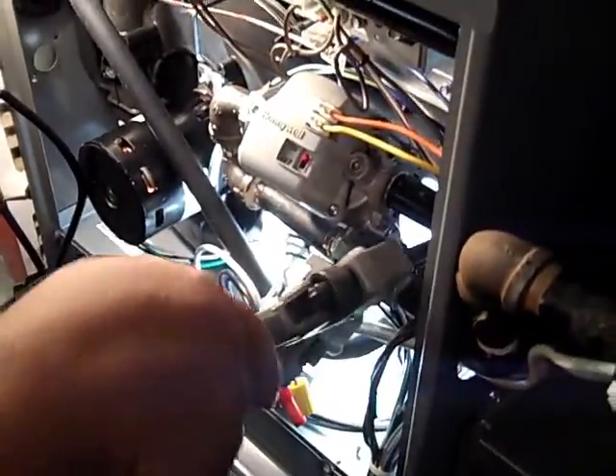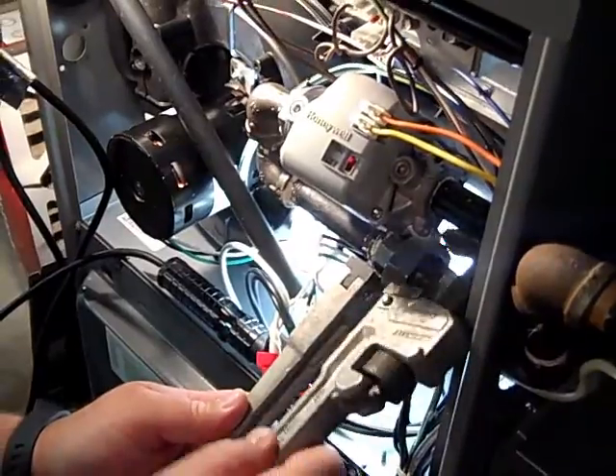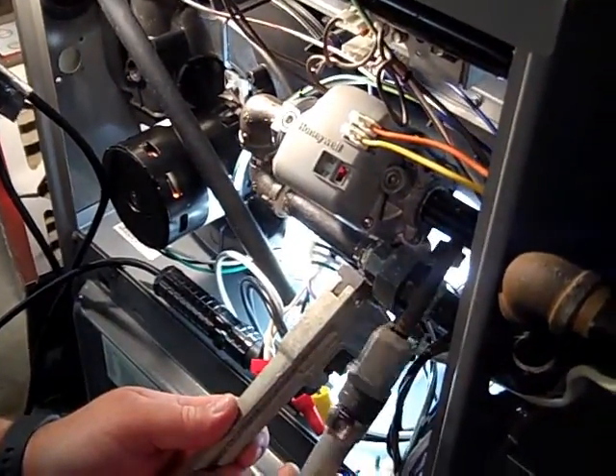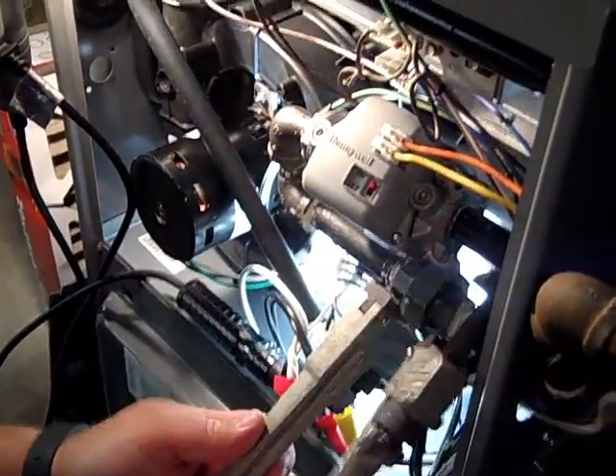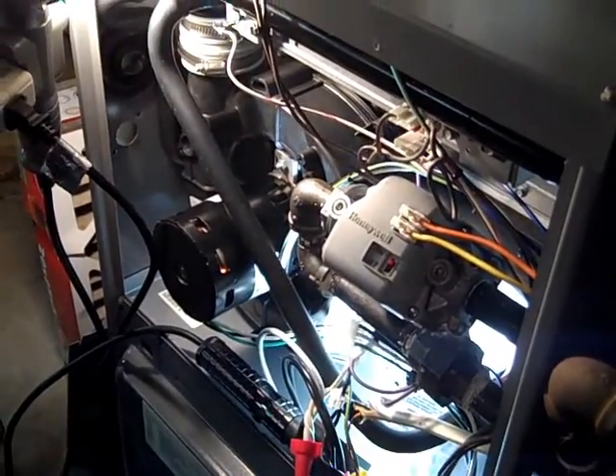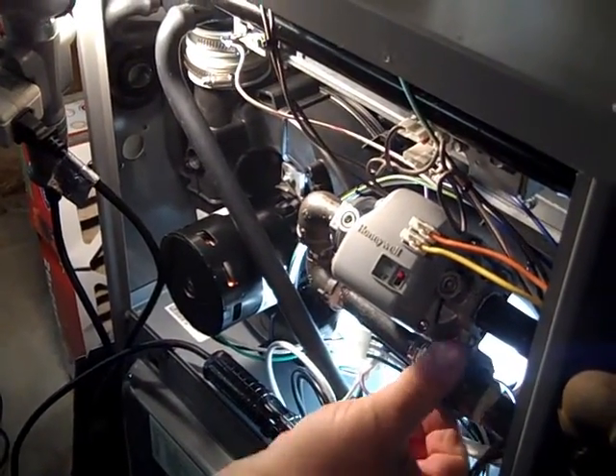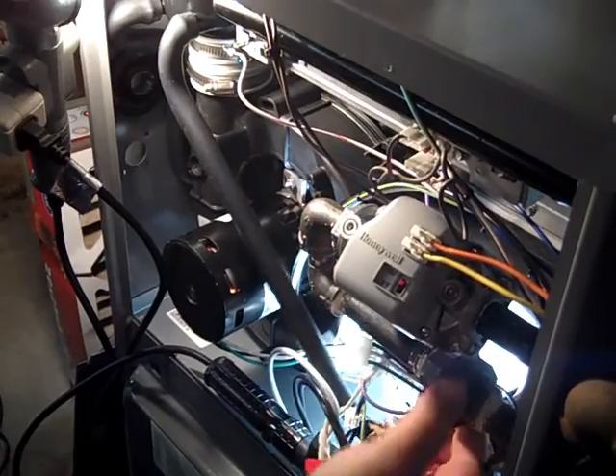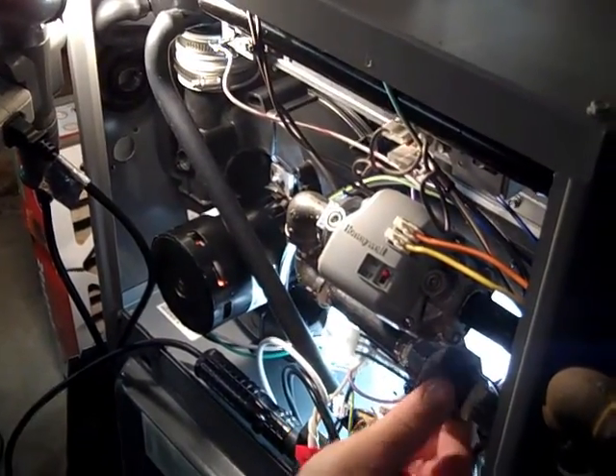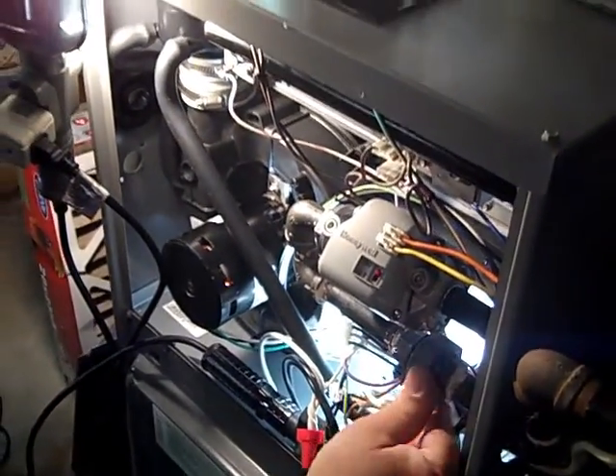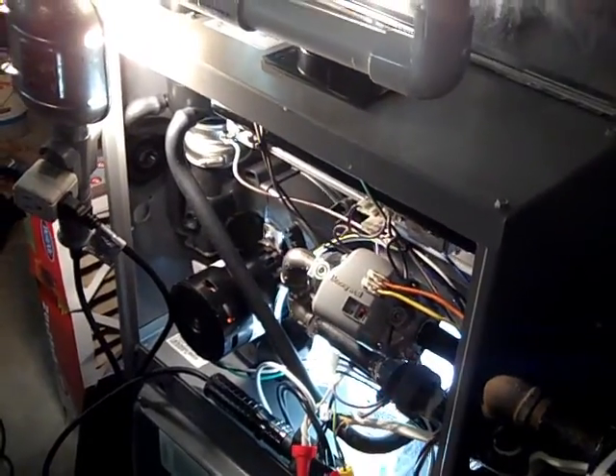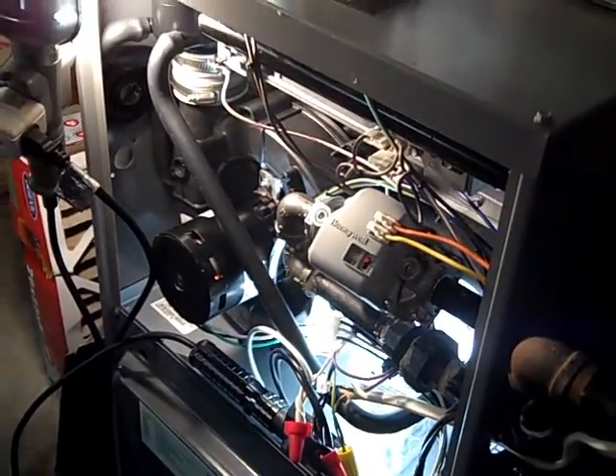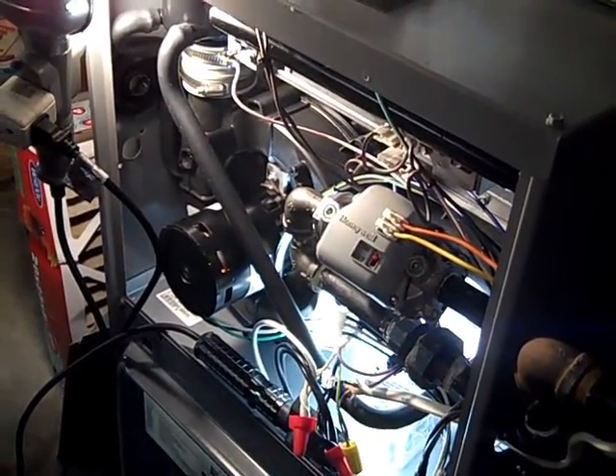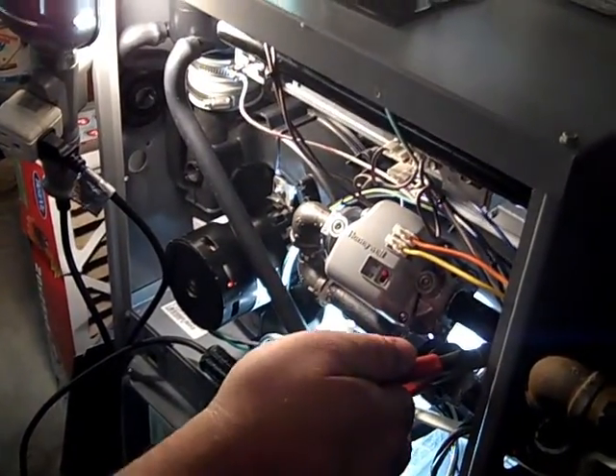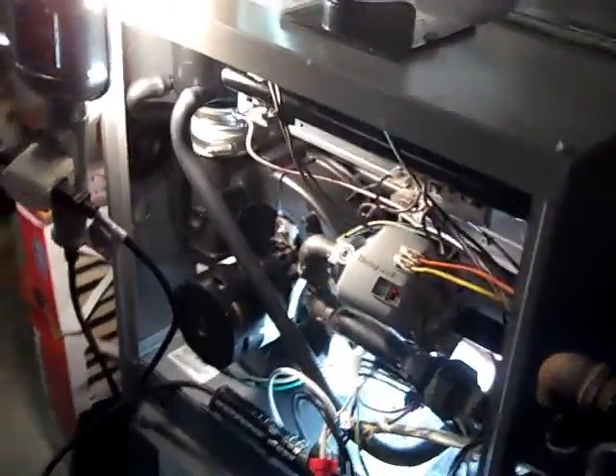Kevin, I see you're taking the gas line apart. In this compact furnace, that's about the only way you're going to be able to pull the burners out, isn't it? This is true for this model. The only way—and especially if you run on propane, you have to wire brush those burners every time. Because propane burns at a higher temperature, they get dirtier faster, and there's a bit more moisture in the gases, I understand.